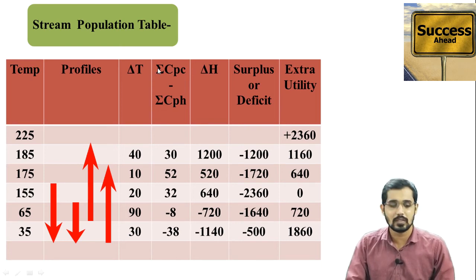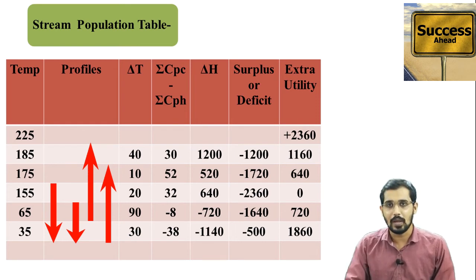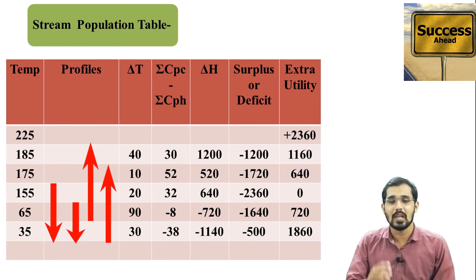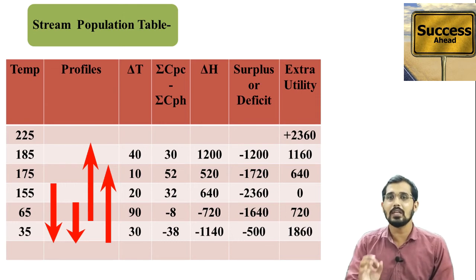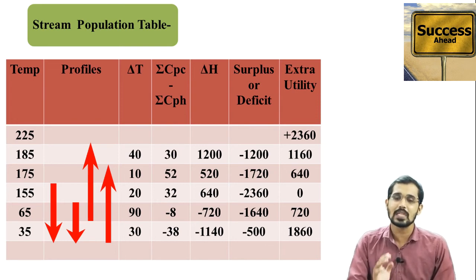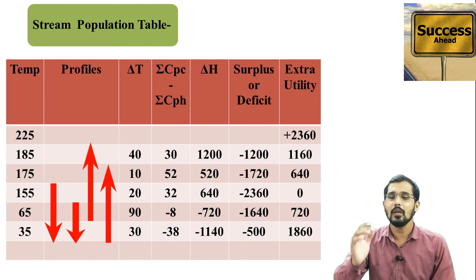In the first column, shifted temperature values are written in decreasing order. After that, temperature profiles are drawn for H1, H2, C1, and C2 streams — and if H3 or H4 streams are available, you can draw those as well. Here, only H1, H2, C1, and C2 were available from the last numerical. After that, we calculated ΔT values using shifted temperature values — for example, 225 − 185 = 40, and similarly all other values.